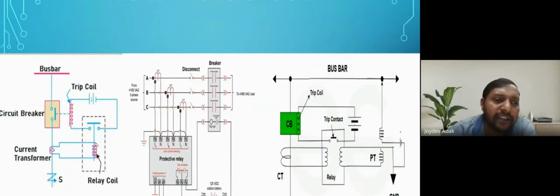The setting is already given previously, during the commissioning of the system. So this relay, if the current in the feeder gets above the setting value, then it will energize and close the contact. If this contact gets closed, then this circuit gets energized. If this circuit gets energized, this coil, connected in the breaker coil, is engaged. Then it will pull the breaker, and the contact breaks.